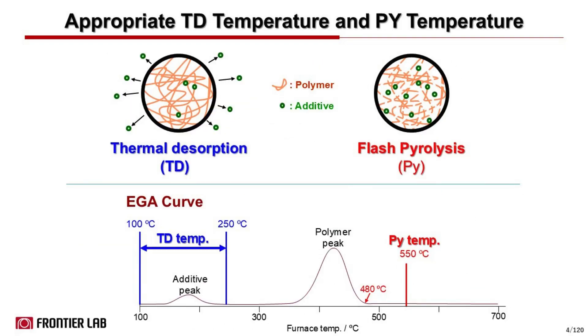In this slide, we show typical evolved gas analysis data of a polymer sample where a small peak at the low temperature range indicates the type of additives present in the sample, and the large peak at the high temperature range indicates the type of polymer present in the sample. This interpretation is possible only due to the average mass spectra that EGA-MS produced.